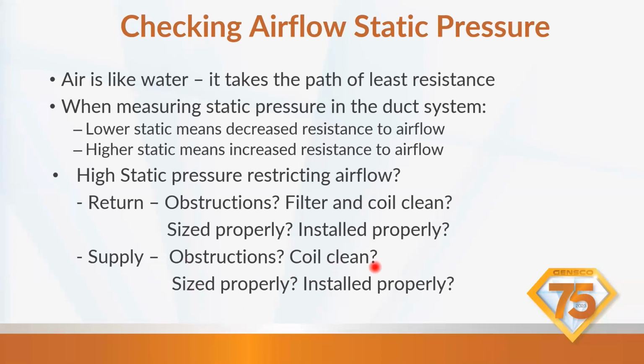Supply, obstructions, coil clean. And these obstructions, I mean, that could be the furniture. That could be somebody setting the couch or a dog bed onto the register so it's not breathing correctly. These are all issues that are going to affect compressor life. It's going to affect compressor pressures. It's going to affect your superheat and subcool.